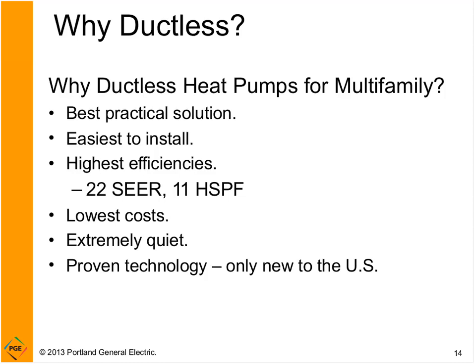a standard heat pump. The HSPF is known as the heating seasonal performance factor, and it's kind of the SEER equivalent for the heating season. And so we're seeing HSPF numbers of up to 11. And the federal minimum right now for HSPF is 7.7. So again, considerably higher efficiency compared to federal minimum standards. And lowest cost. It's probably going to be the lowest cost option if you're looking to improve efficiency over electric resistance, baseboard, wall heaters, and ceiling cable heat.